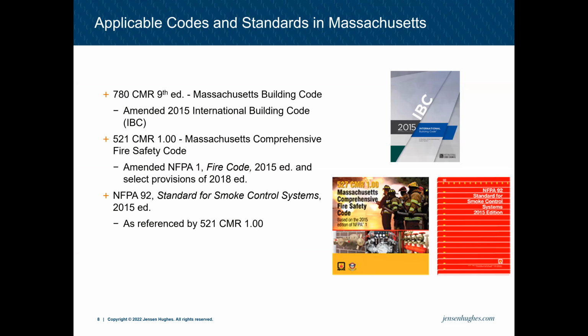So for everyone's favorite topic, we have the applicable codes and standards relating to smoke control. Our biggest related ones are the International Building Code, or the Building Code, the Fire Code, and NFPA 92. In Massachusetts, the Building Code is 780 CMR, and currently we're in the 9th edition, which amends the 2015 International Building Code. Our Fire Code is 521 CMR, which amends the NFPA 1 2015 edition with select provisions of the 2018 edition. And NFPA 92, the standard for smoke control systems, is a reference standard in 780 CMR, and that would be the 2015 edition, as also referenced in 521 CMR.